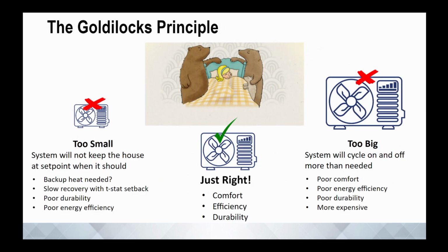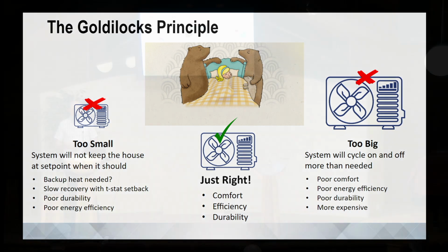So, sizing of equipment. On the left side, the system's too small. You're going to run into challenges with backup heat potentially being needed, and durability and comfort issues, because if it's a little bit too small, some people might be fine turning on a space heater or fireplace, but not everybody wants to operate their house that way. They like that automatic, set-it-and-forget-it experience we're used to in modern life, for better or worse. On the right-hand side, too big.